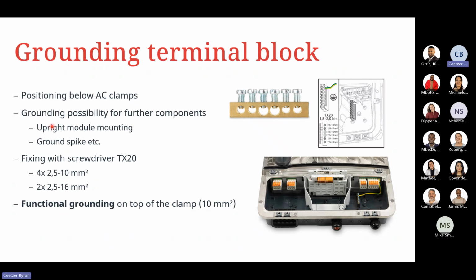So also what's handy is what we call the grounding terminal block. This is positioned below your AC clamps. So it's your grounding for further components if need be, so ground spikes, upright module mountings. You've got 2 fixing screws, so it's Torx 20. You've got 4 holes that will accommodate 2.5 to 10 mil squared cable coming in, and 2 that can accommodate 2.5 to 16 mil squared earthing cable that's then required additionally for the unit.